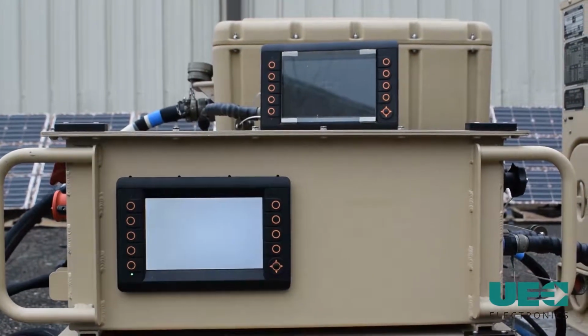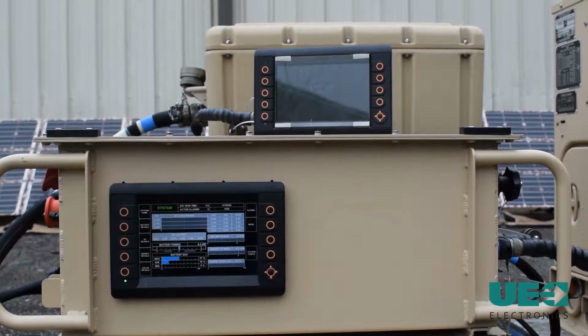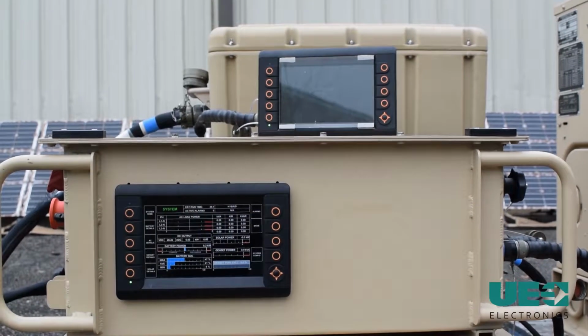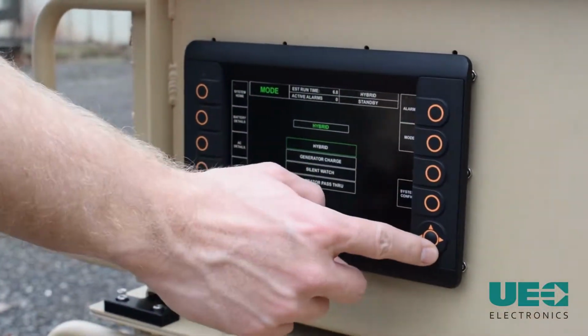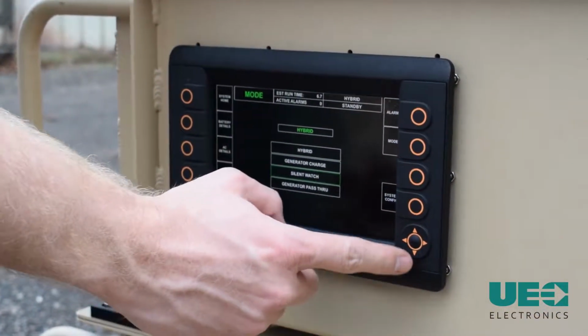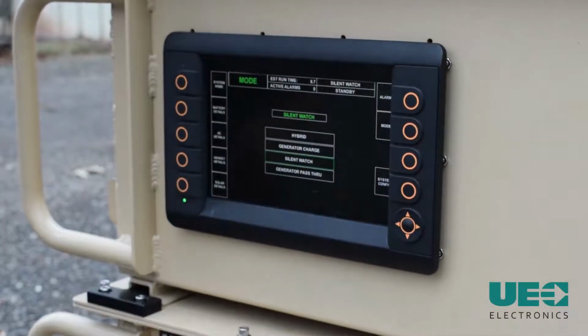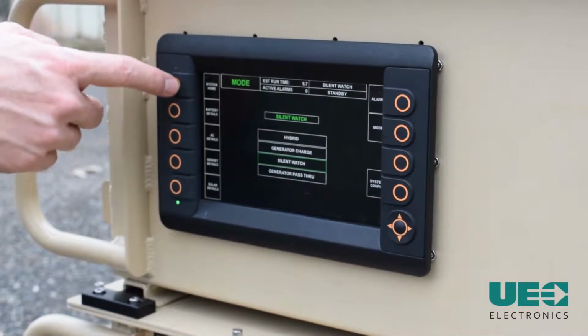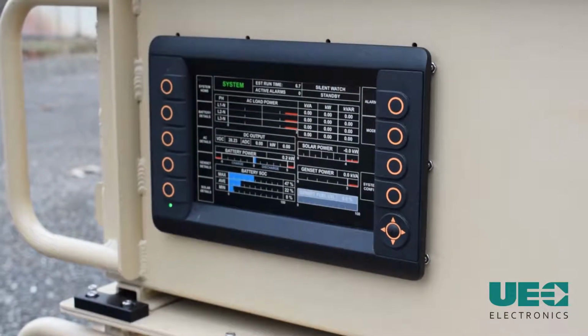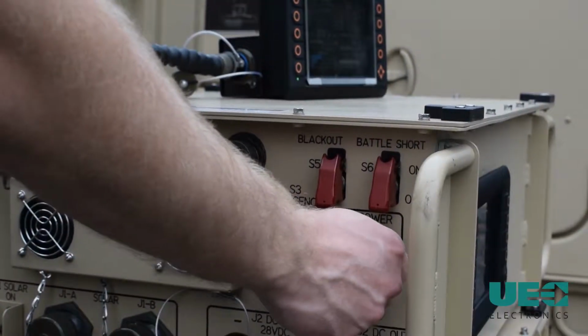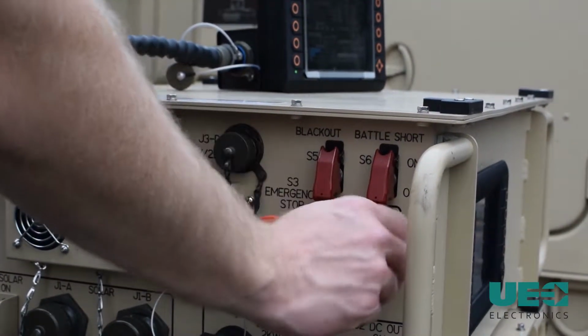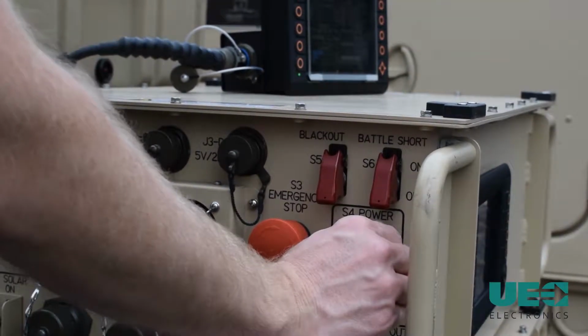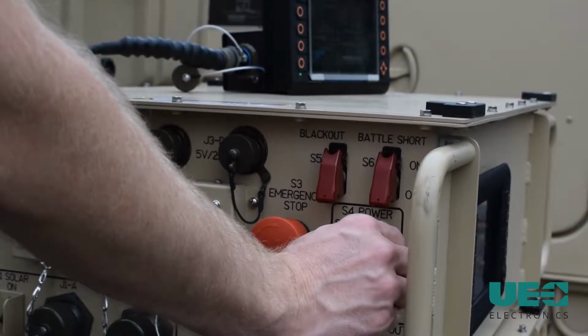The HMI display will turn on. Wait for standby to appear in the upper right corner. Use the mode button on the HMI to select hybrid, generator charge, silent watch, or generator pass-through. To run the system in the selected mode, move the S4 power switch from standby all the way up to the start position. Hold for 2 seconds and then release the switch.